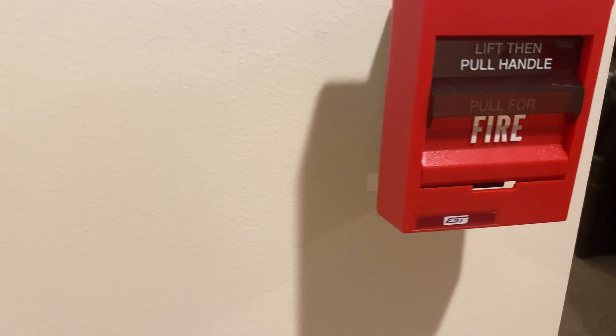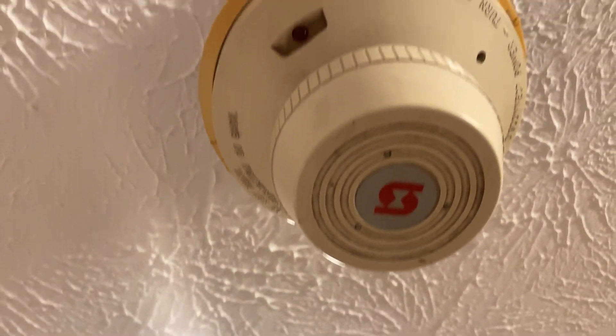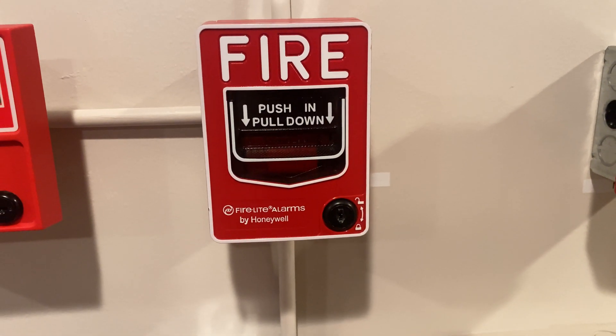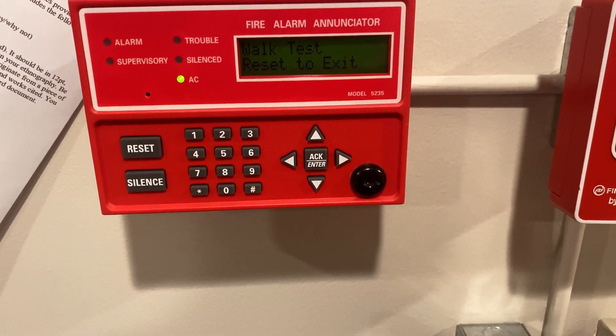Over here we have the EST 278 dual action pull station - we'll be pulling this today. Up here, an oldie but a goodie: the Simplex 2098-9577 ionization smoke detector, and we will be saber testing this today. There's the LED going - still works, a little slow but still going. Over here we have the Gentex Commander 2, 75 candela version, a fixed candela strobe flashing at 75 candela. Coming down here we have the FireLite BG-12L key locking dual action pull station by FireLite Alarms. We are still in walk test - let's get rid of that from the annunciator. System normal - awesome.